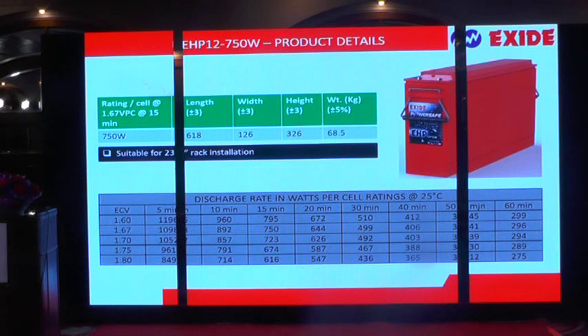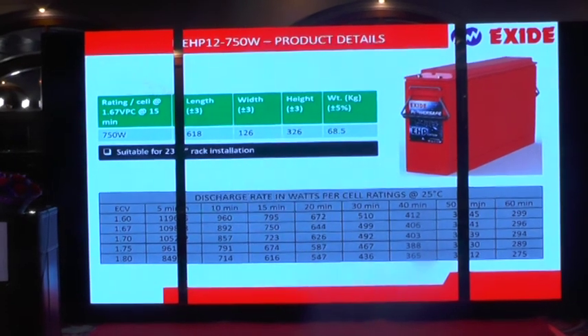Considering the standard OCV, open circuit voltage, as 2 volt and the end of discharge voltage as 1.6 volt, with an average discharge voltage of 1.8 volt, this translates to around 700 watts for 5 minutes, which is very high power. I can tell you no available VRLA product can provide this power at this point.